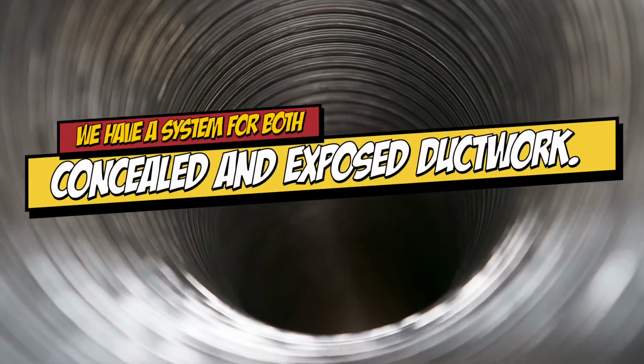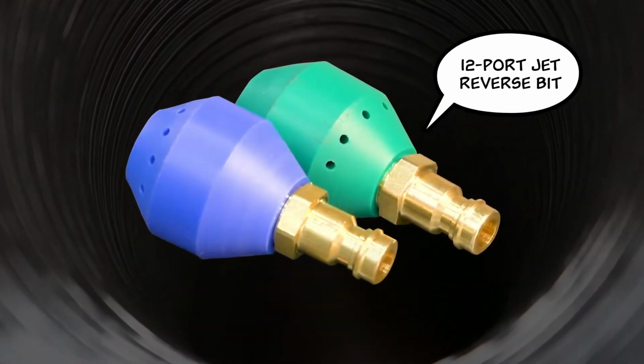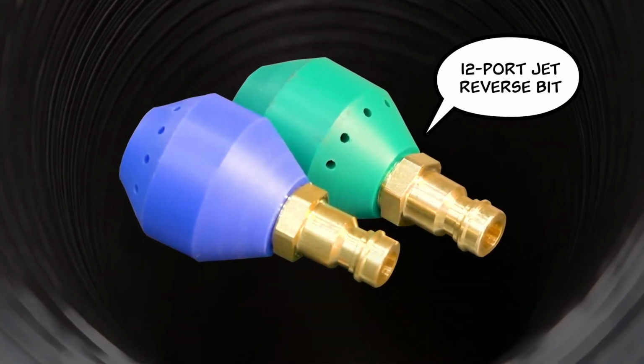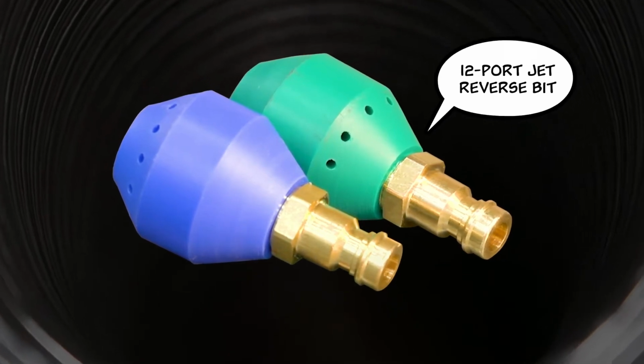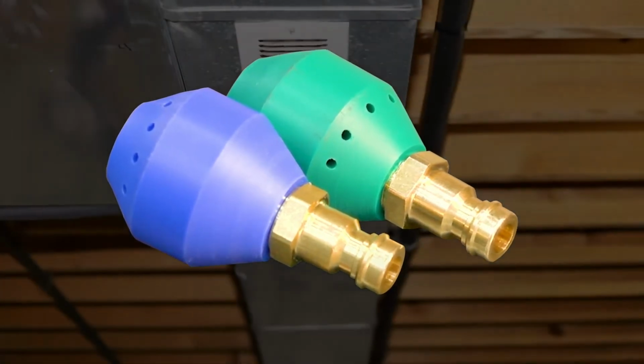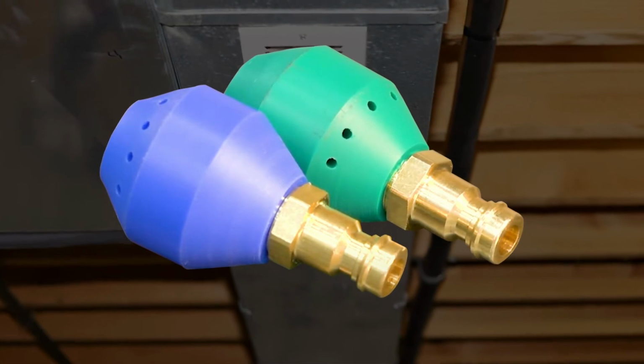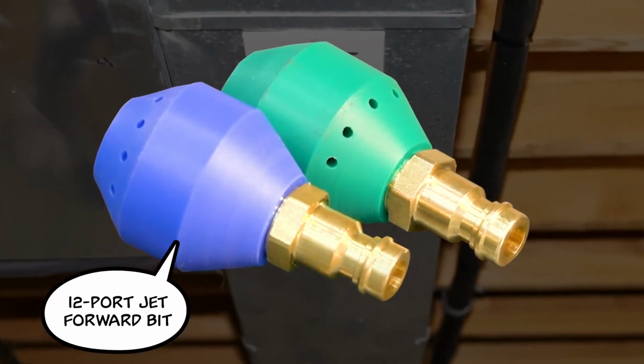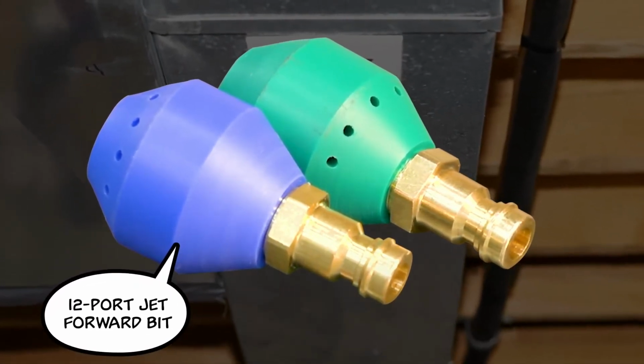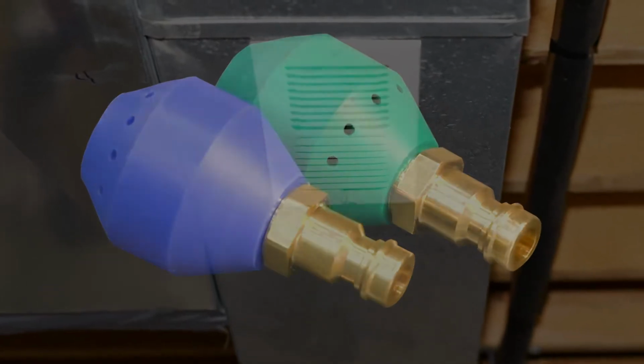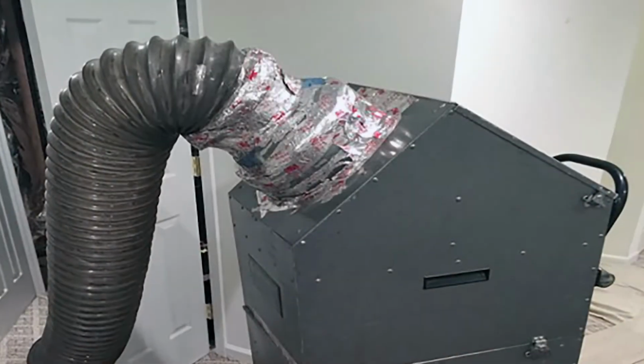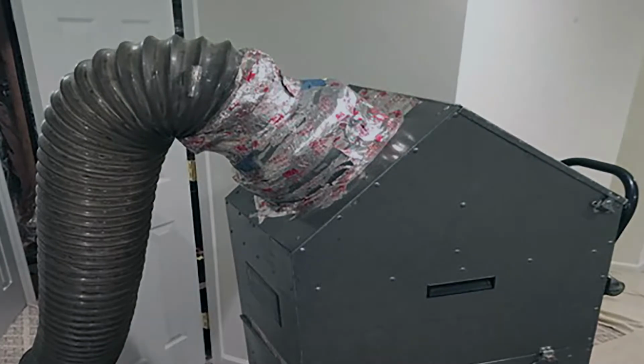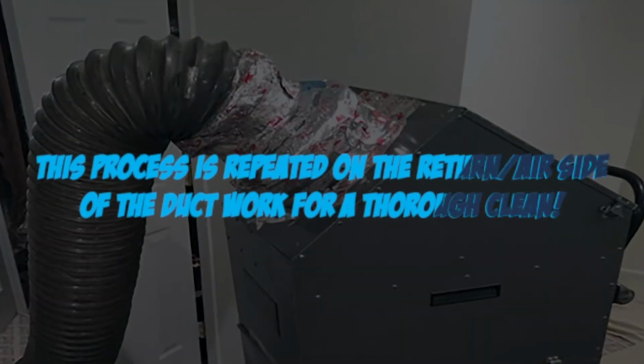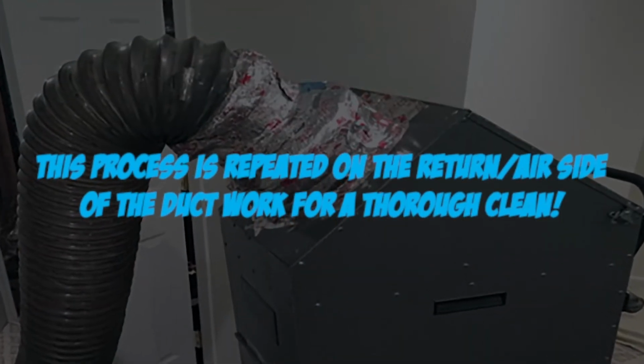We have a system for both concealed and exposed ductwork. If your home's ducts are behind drywall, we'll use a reverse bit, which means the hose will be sent down the main supply air trunk, and as the hose is pulled back, the reverse bit pushes the debris. If you've got an open basement where ductwork is exposed, we use the forward bit, starting at the end of the supply air trunk and working our way back to the HVAC equipment, pushing debris as we go. For both methods, the vacuum collects the debris along the way. This process is repeated on the return air side of the ductwork for a thorough clean.